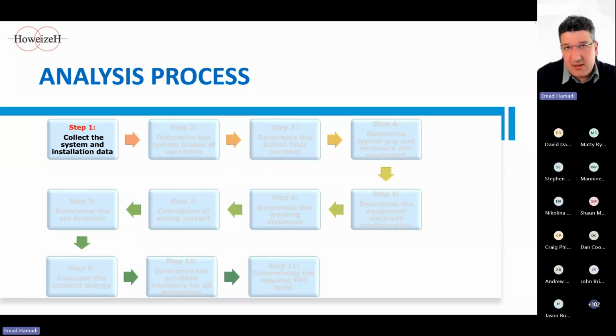Even for new facilities, field verification of the single line diagram with the protection settings is necessary to ensure integrity. In general, the data required for an arc flash study is extensive. Key elements like the single line diagram, the fault current, X/R ratio for the sources, and nameplate data from the transformer, generator, large motors, etc. are required. Additional information like the enclosure size, electrode configuration, cable data, CTs and VTs, and the protection devices is also critical. And as I said, field inspection may be necessary to verify all of these: the fuse type, circuit breaker settings, protection relay settings, etc.